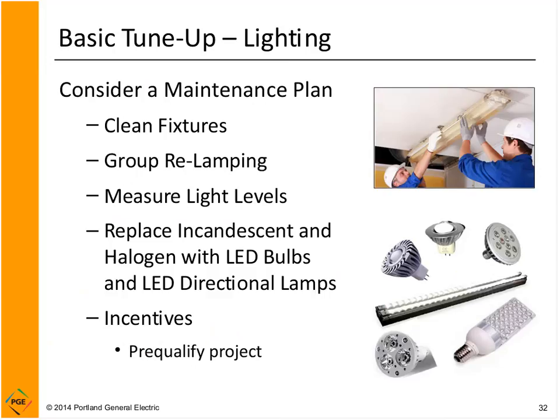Group relamping: if we're talking about light fixtures 30 feet up in the air, if one lamp goes out, odds are its neighbors will go out relatively soon. In that case, you may not want to drag out the lift or rent it again, you may as well change out fixtures you know are going to fail soon. Then you want to measure light levels. Like I mentioned before, you may have an office building converted to a warehouse, where the office needs additional lighting and the warehouse doesn't, but the lighting may not have been changed out. So be sure to measure those light levels.